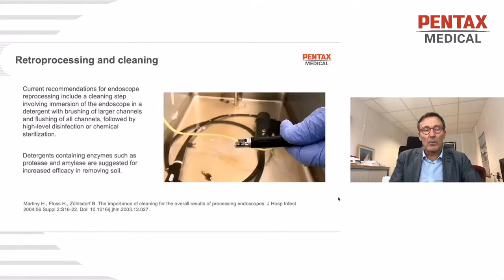So what about reprocessing and cleaning? Current recommendations for endoscope reprocessing include a cleaning step involving immersion of the endoscope in detergent with brushing of larger channels and flushing of all channels, followed by high-level disinfection or chemical sterilization. We know that flexible endoscopes are complex devices, difficult to clean, but it's very, very important to clean, dry, and store them because they are reused in patients.